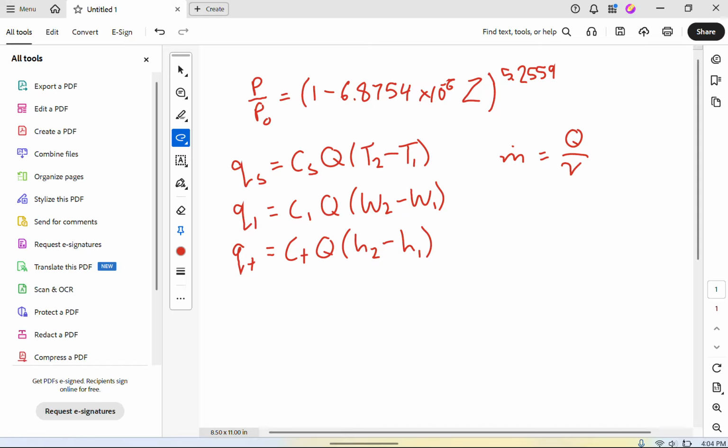Your specific volume can be determined through your psychrometric chart. However, the specific volume does not change that much depending on temperature and humidity. It does change, but the changes are fairly small. So you actually can take an approximation of your weighted average with just the airflow value in terms of CFM.